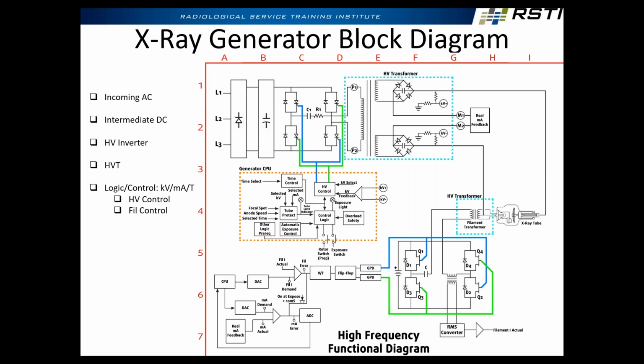Same thing. Exactly. Yep. Yeah, high voltage multiplier, high voltage transformer, HVT, all different names that they'll apply for that. Yep. So that would be this guy, the multiplier. Where have you heard that before? Was it Hologic? Because that's what they call theirs. So Hologic calls it the inverter and the multiplier. Well, you can see right here, this is what they're doing. What's the inverter doing? Chopping up that DC. What's the multiplier doing? Stepping it up.